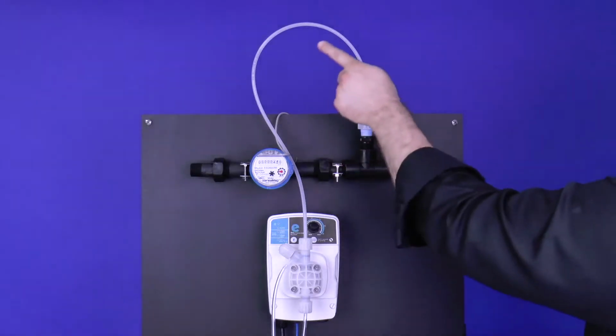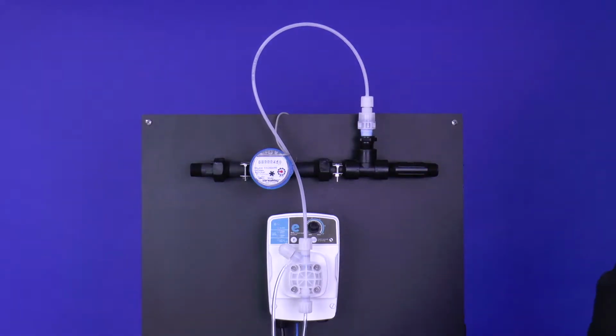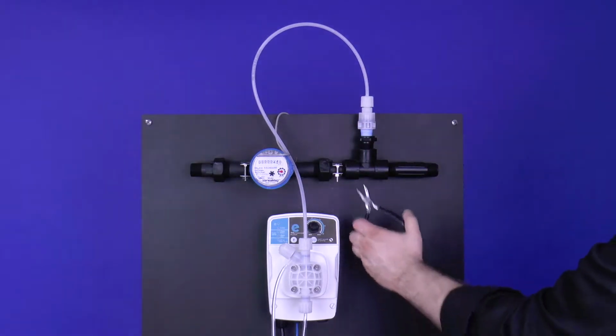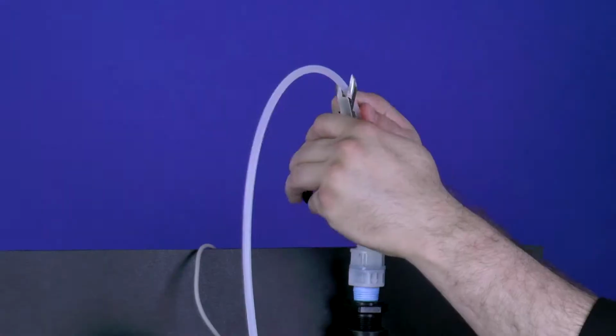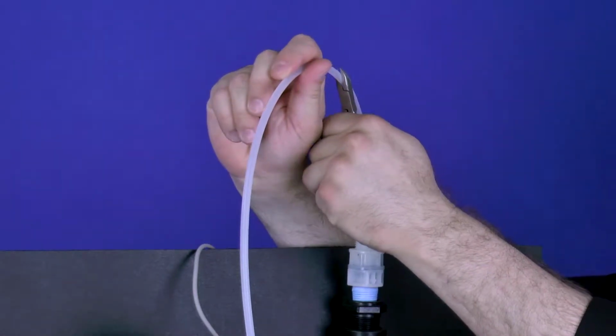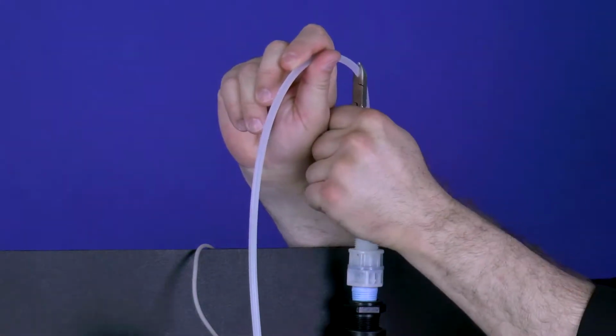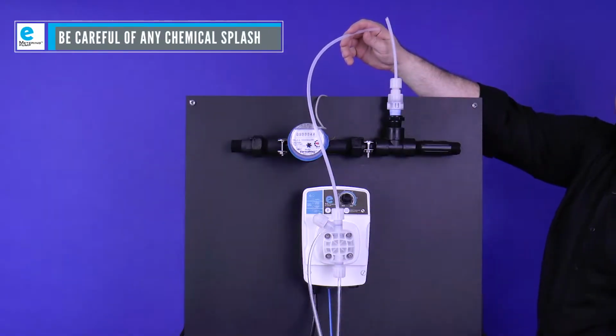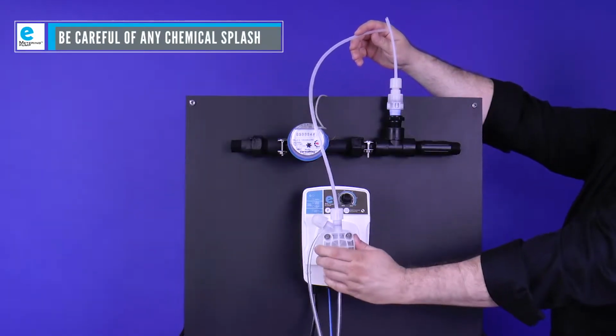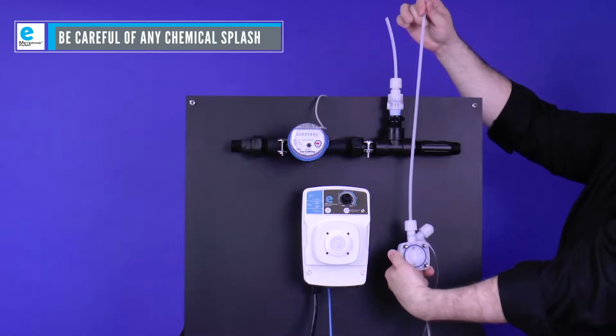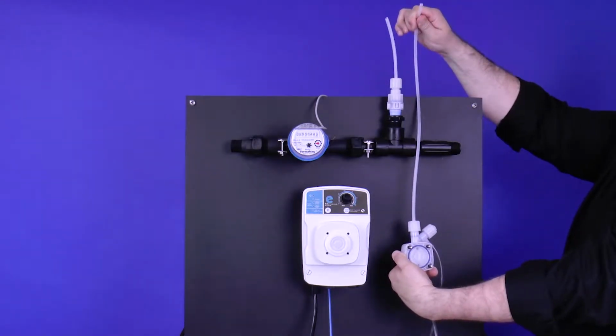Locate the used rigid discharge tubing connected to the old injection valve. Use the diagonal pliers or cutters to cut the tube as close to the old injection valve as possible. Keep the tube upright to ensure no remaining chemical spills out. Set the diagonal pliers down and use the same hand to remove the pump head along with the connected tubing and foot filter. They should all come off as one piece.